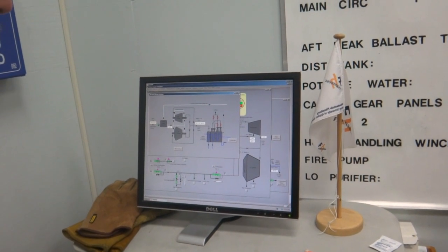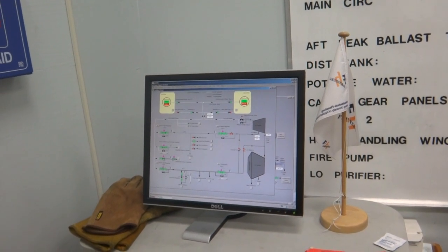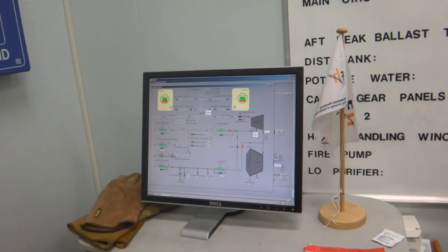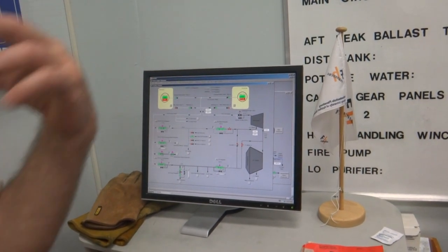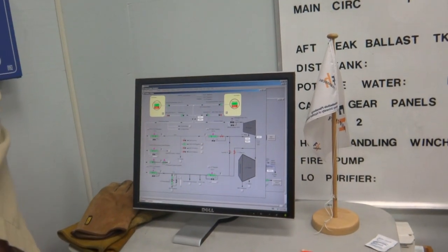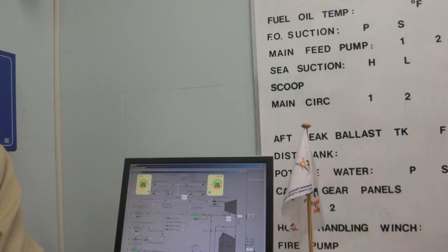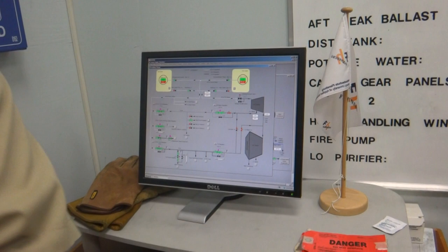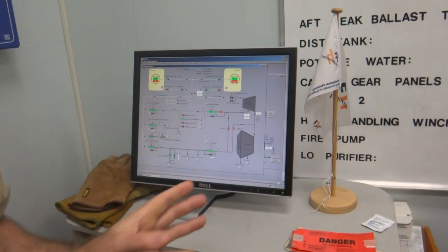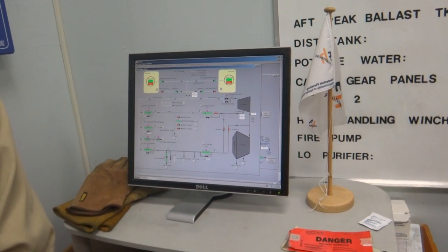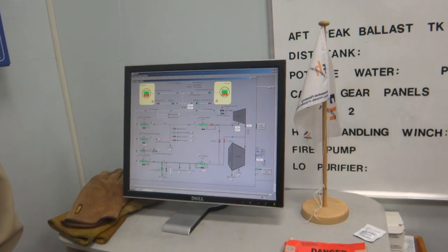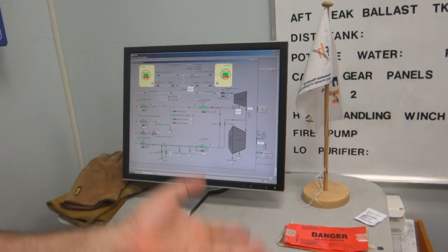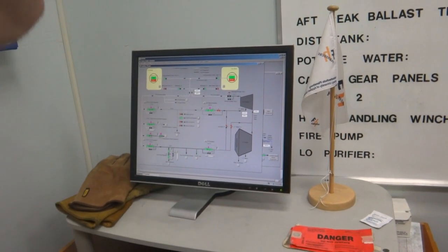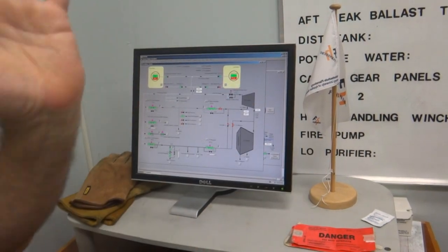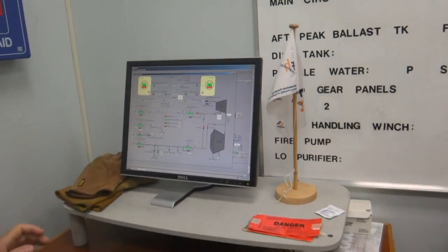And you'll use more gland seal in port than you will at sea. Because in port you have vacuum all the way back to the throttle valve on the high pressure turbine. High pressure turbine's in a vacuum now. At sea that's not the case. That's under a positive pressure and the low pressure turbine only would be in a vacuum. So you actually need more gland seal, depending on the load at sea. And there's a regulator to dump or add, which we'll talk about in the part task trainer.